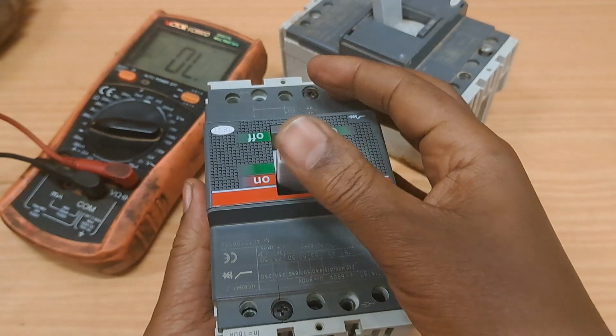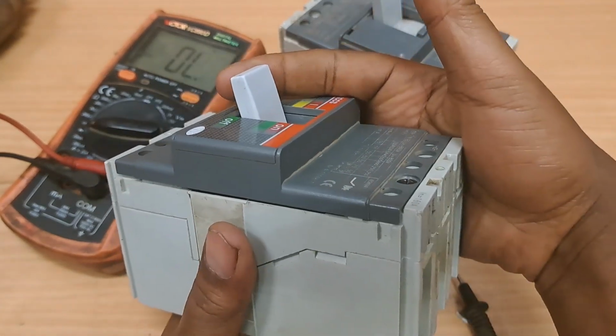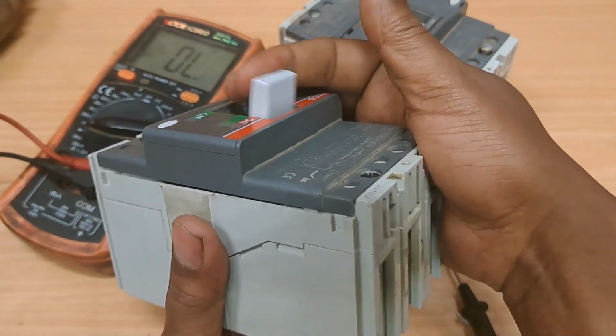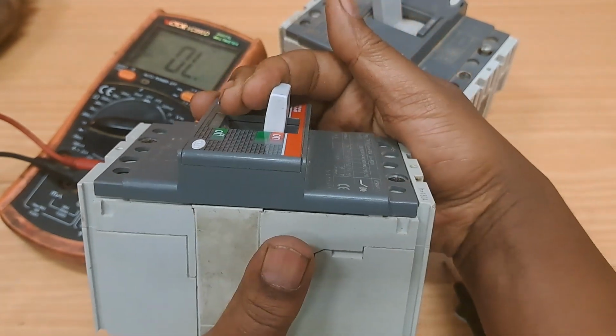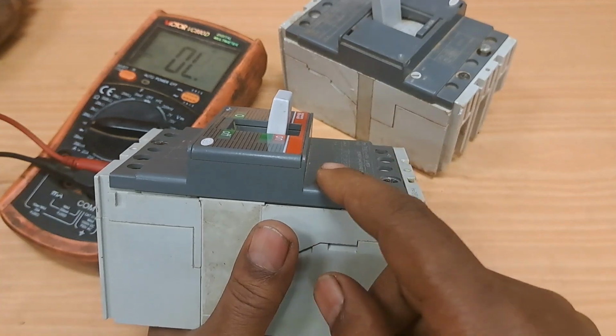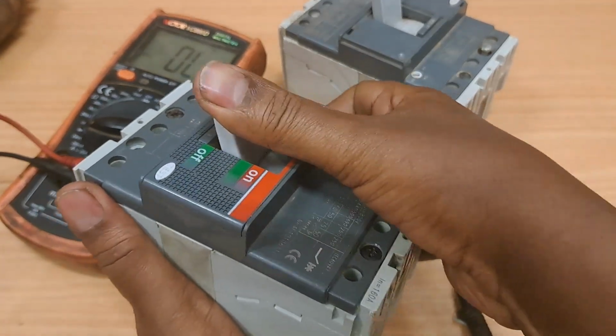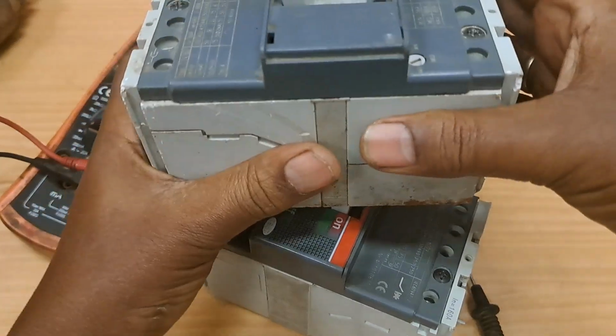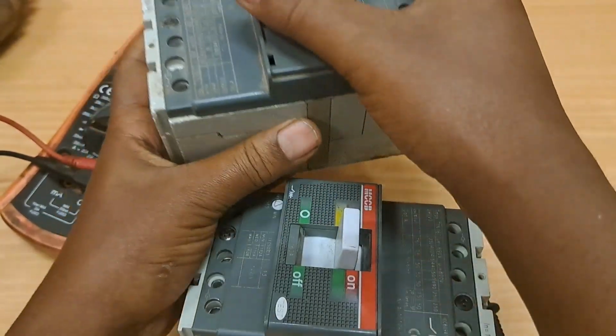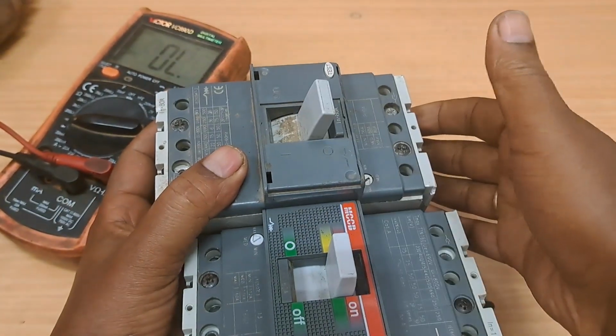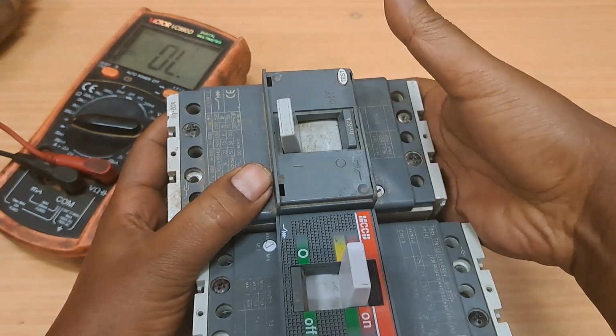As you can see, it is not latching nicely to the on position. It is not reaching fully on. See, it is not fully on. It means this breaker is defective. Look at the difference. Right here, we have a very nice latching. Look at here. Snaps off, snaps on.